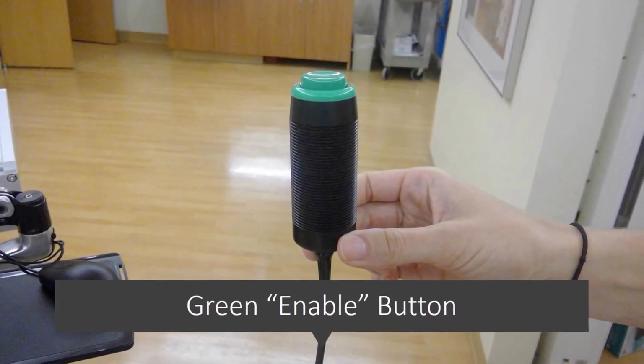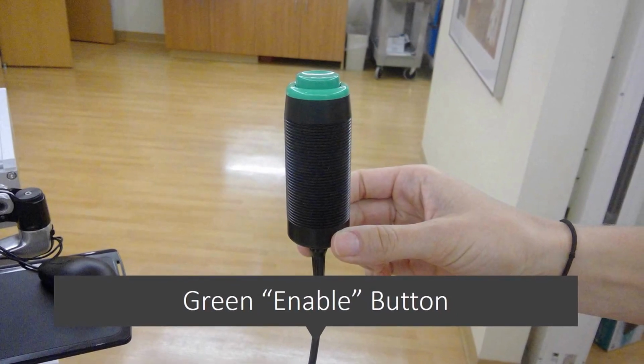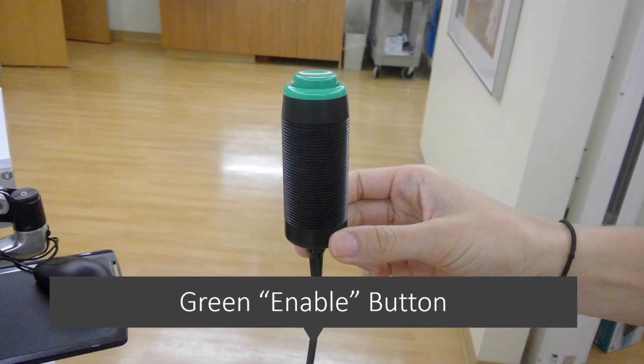This button is what puts you in charge of the whole process. When you are ready to begin, the therapist will instruct you to push your button in. This alerts the ABC system to start. The therapist will then instruct you to take a few normal breaths, followed by a breath hold. When you reach threshold on your deep breath in, the system will aid you in staying at that level until you let go of the button and the system releases and you are able to breathe freely. If at any point during the treatment you need to breathe, or if there is an emergency, just let go of the button and the treatment will stop.